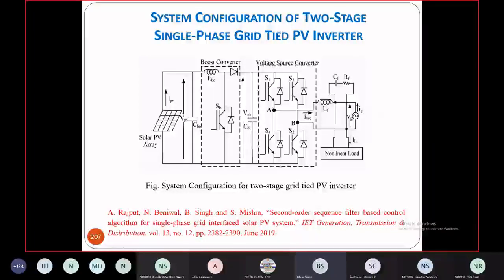So what we found is, if the DC link voltage varies within a certain range proportional to the AC voltage, we are able to reduce losses by 3 to 4% in the inverter. However, the boost converter increased losses by 1%. So overall, we are able to reduce total losses by around 3%.